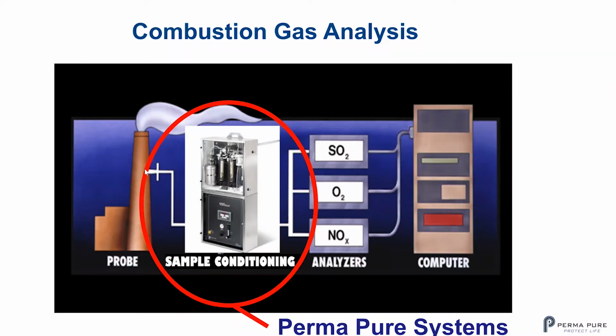Now, the samples coming off the probe are dirty, wet, and hot, and they need to be cool, clean, and dry for the analyzers. And so the job of the sample conditioning system is to prepare that sample for the analyzers. And that's where we play, the probe and the sample conditioning system.